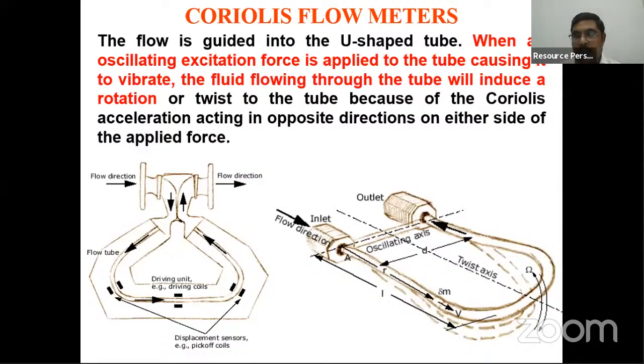Here, the oscillation of the fluid is measured in terms of the frequency shift. By measuring the oscillation of the fluid, you can directly measure the mass. Basically, the Coriolis mass meter consists of a U tube which is set to vibrate at a constant frequency.